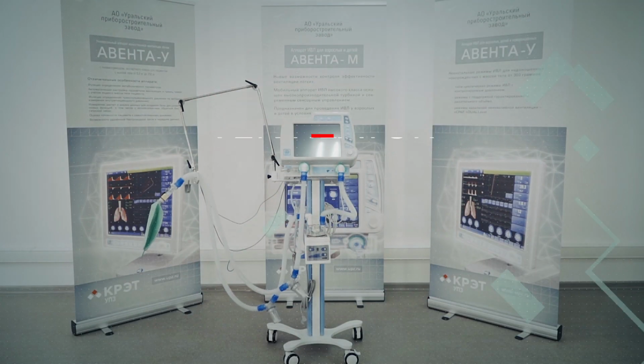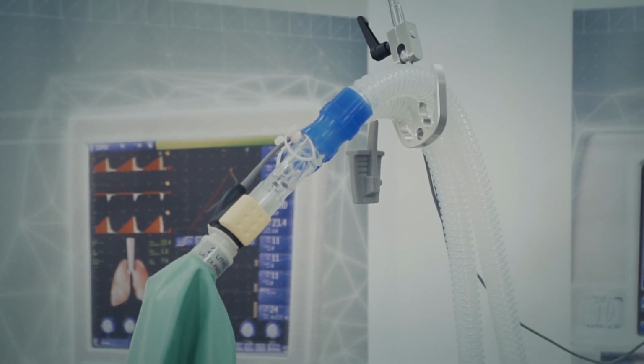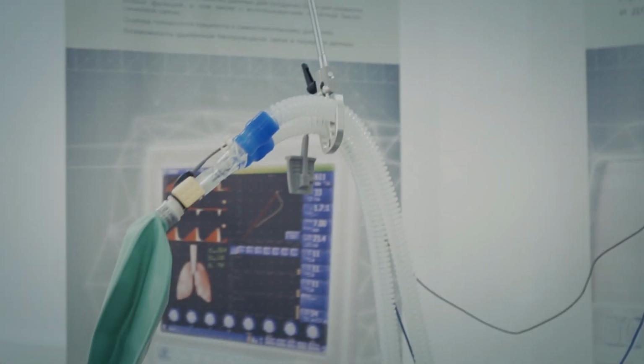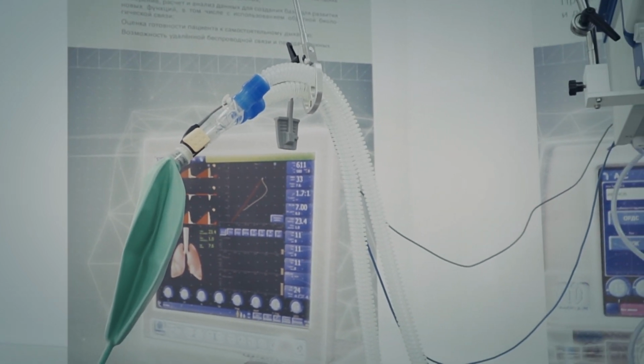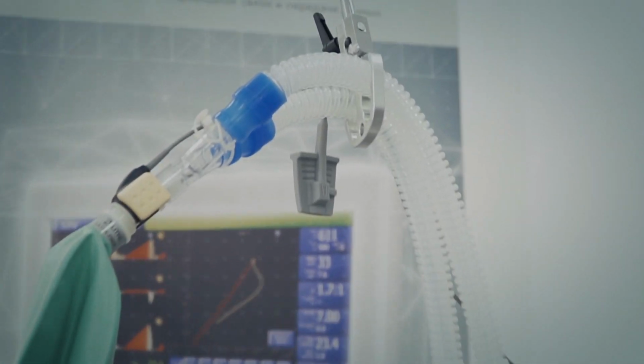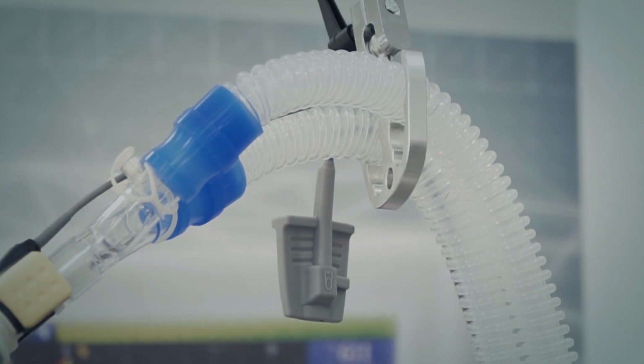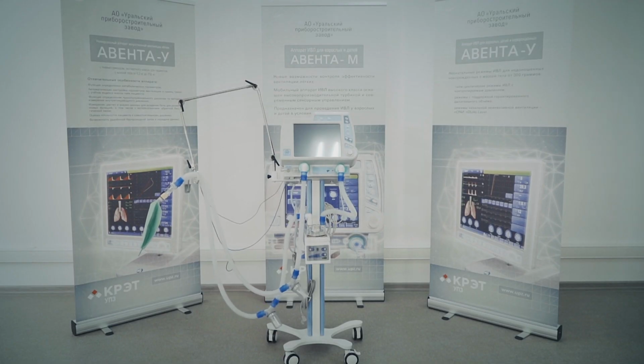Prior to the ventilator first use, its disinfection is recommended. During operation, external surfaces of lung ventilator, holder of breathing circuit, expiratory valve, patient's breathing circuit, moisture collectors, masks, humidifier chamber, flow sensor, capnography and pulse oximetry sensors, gas delivery hoses and connectors are subject to cleaning and disinfection.